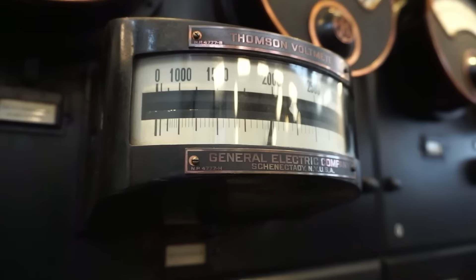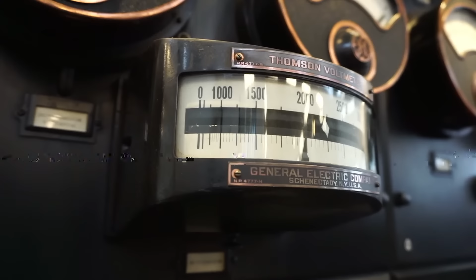Now the internal oil pump is handling the lubrication. Now we are following the start-up current, just now 100 amps, and at about 90 amps, Anders will connect two rectifiers, one for 500 volt DC and one for 125 and 250 volt DC. We are moving to the other side of the control panel, and Anders will connect the knife switch, and with that he's magnetizing the 500 volt DC rectifier to energize the motor with 2300 volt.